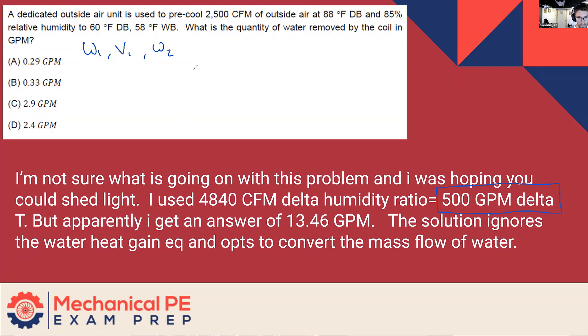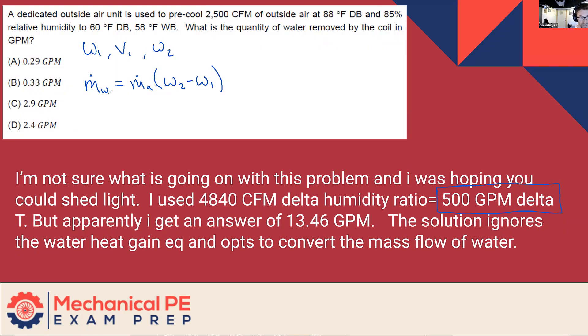Now we have air flowing over the coil. We can write the formula that needs to be used here. I won't say memorize — I think you should internalize it. I expect you'll encounter this enough that you'll end up remembering it without really trying. This is saying that the mass flow rate of water vapor is equal to the mass flow rate of air times the delta of the humidity ratio.